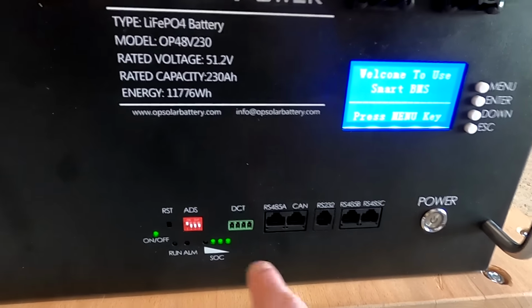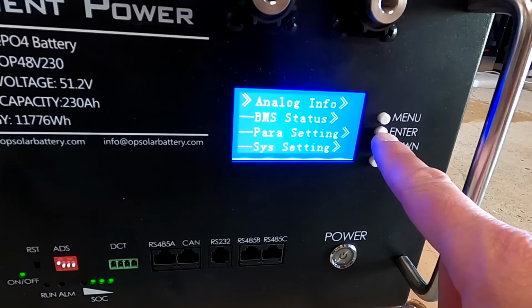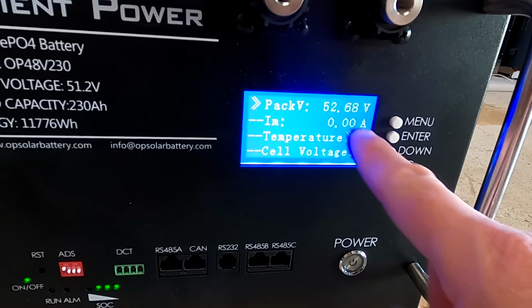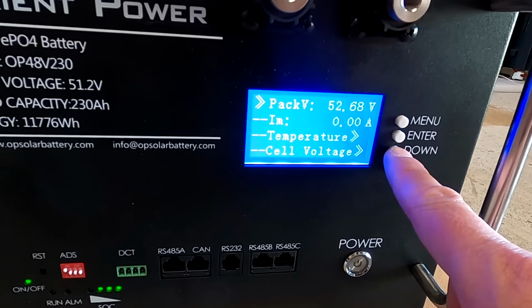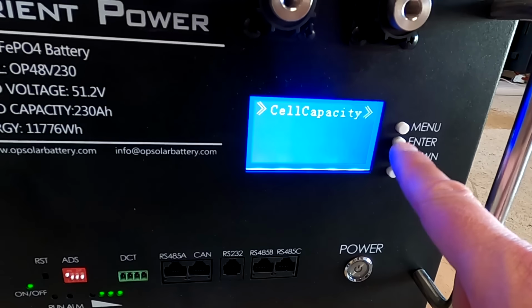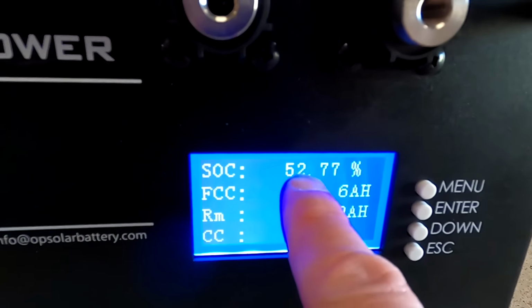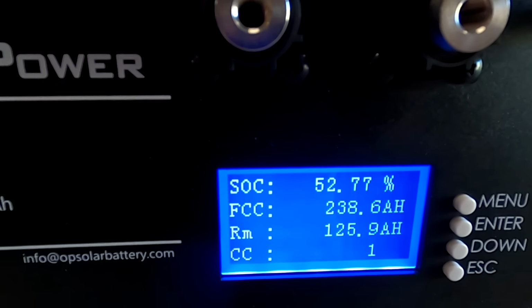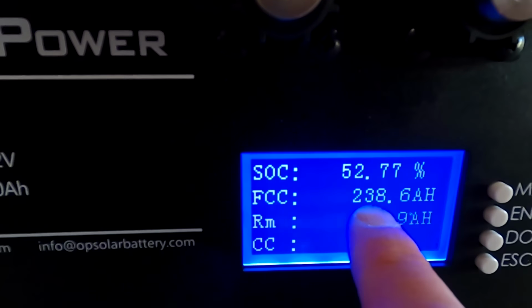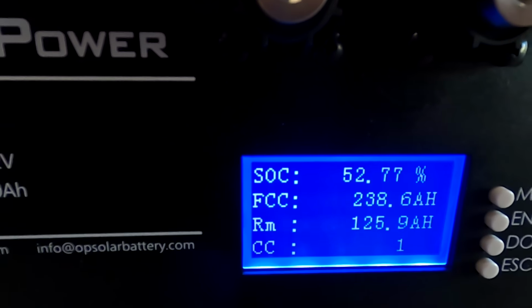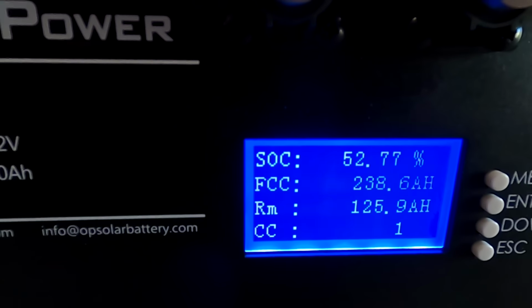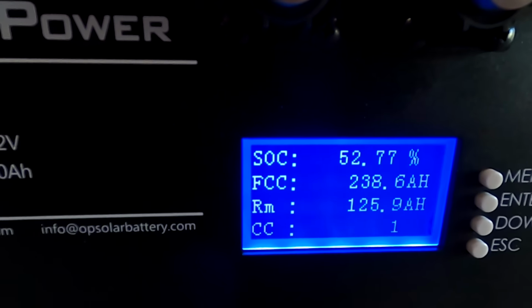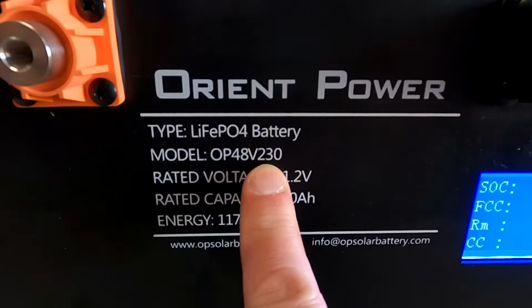Okay, let's turn it on. Doing a self-check. 3 bars we have. Enter, enter. 52.6 volts and 52.7% state of charge. It has been tested with 238.6 ampere hours measured by the BMS during a discharge test. It is a 230 ampere hour battery, but measured at 238.